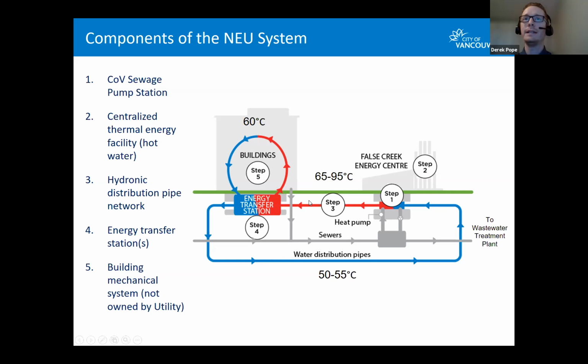Leaving our plant, we have hot water that ranges between 65 to 95 degrees Celsius. That water gets pumped to our customers, and in each building we have an energy transfer station, which is the interface between our thermal grid and the building systems. It's basically a couple of heat exchangers that the building can use to pull thermal energy off of our grid for the building's heating systems and domestic hot water.